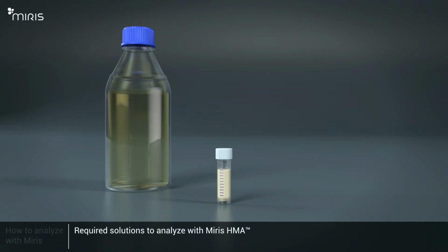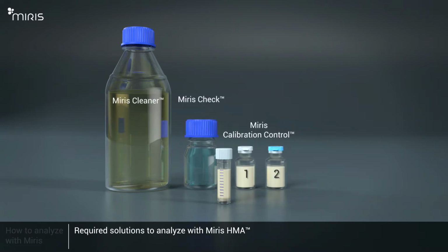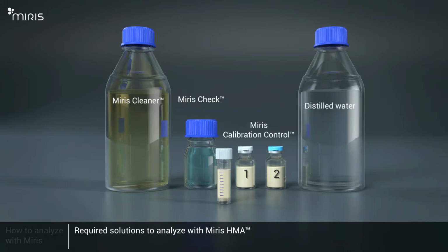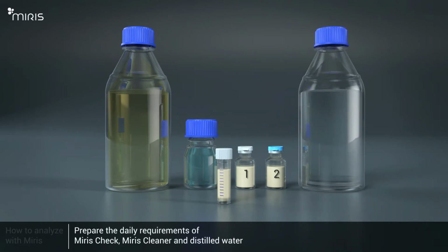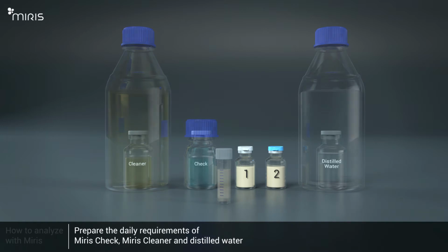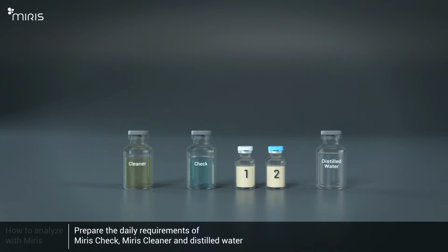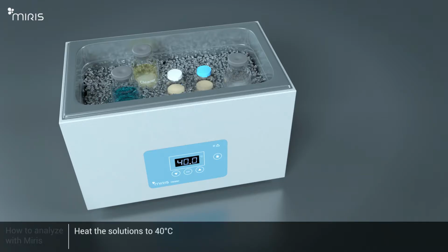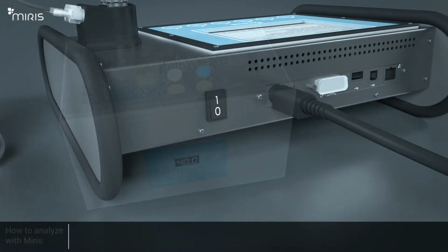These are the required solutions to use with the Miris Human Milk Analyzer. Miris Cleaner, Miris Check, Miris Calibration Control, Distilled Water. Prepare the daily requirements of diluted Miris Check, diluted Miris Cleaner and distilled water, and pour the solutions into smaller bottles for easier handling. Heat Miris Check, Miris Cleaner, Miris Calibration Control and distilled water to 40 degrees Celsius.